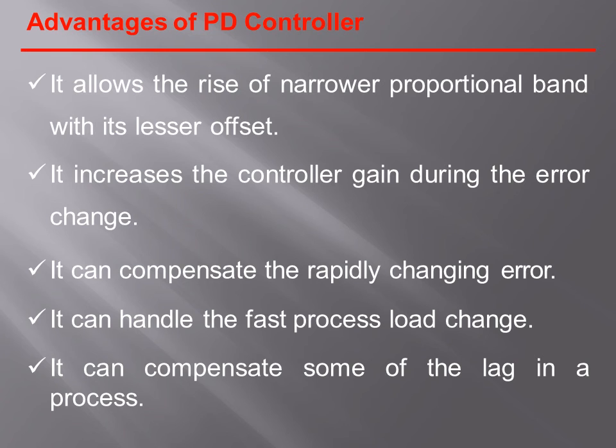Then advantages of PD controller. It allows the use of a narrower proportional band with lesser offset. It increases the controller gain during the error change. It can compensate the rapidly changing error. Then it can handle the fast process load change. It can also compensate some of the lag in a process. So these are the advantages of PD controller.